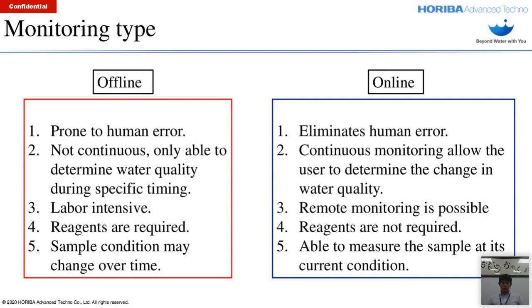For point number four, depending on the equipment used, reagents may be required for offline monitoring. For our online monitoring products, reagents are not required. And last but not least, for point number five, for offline monitoring, the sample condition may change over time, causing the sample quality to be different when it reaches the lab for analysis. On the other hand, online monitoring enables the measurement of the sample in its current condition, which provides the most accurate data of the sample at any given time.